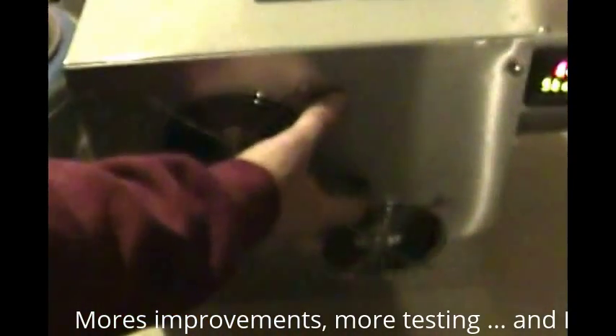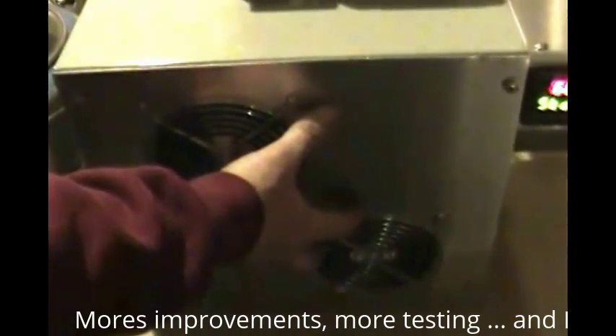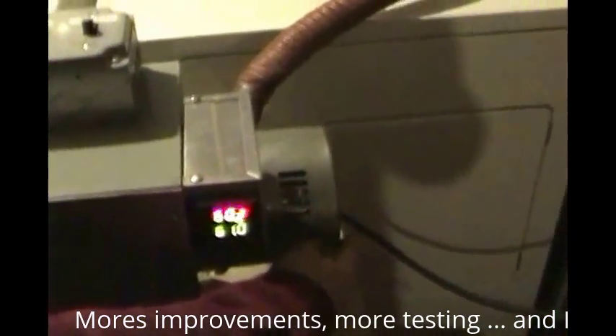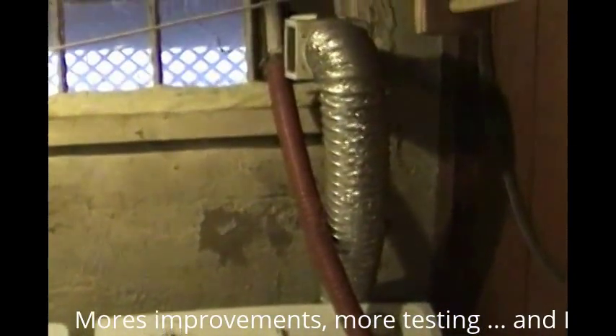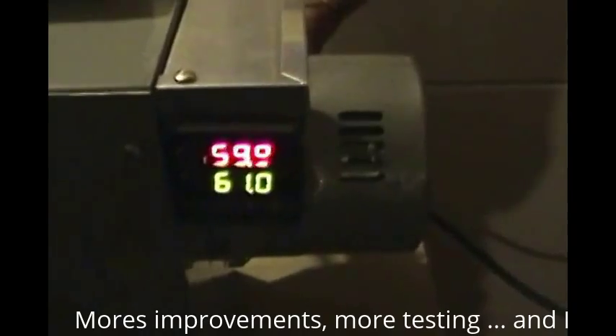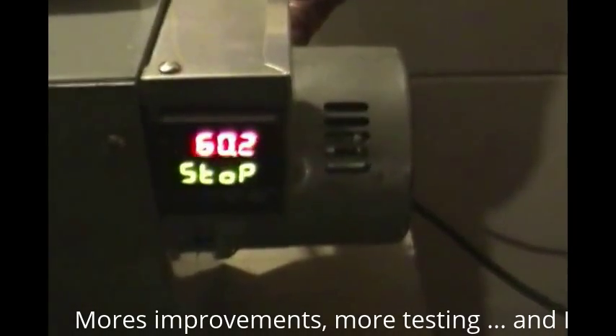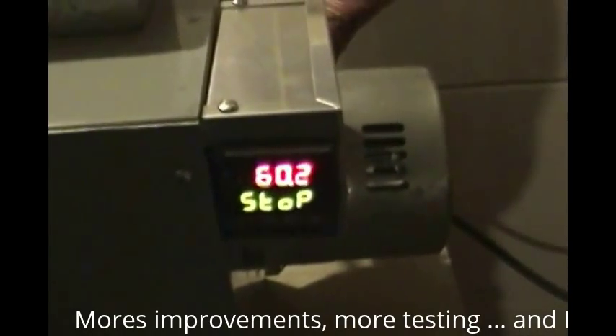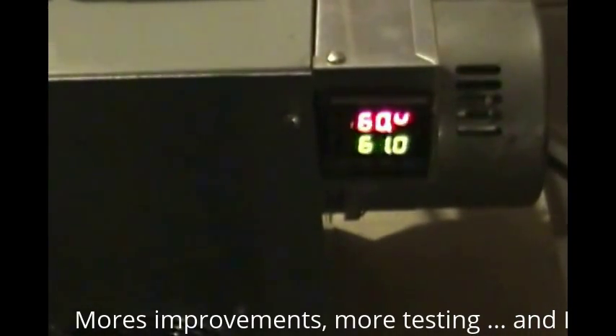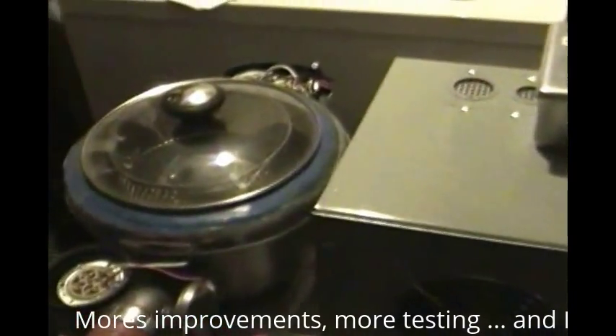There's a special cooling chamber inside of here that cools the exhaust prior to its exiting through the vacuum system that we have, and the hot air and the exhaust just gets shot out through that thin tube outside. Here's our PID. It's programmed to get up to 300 degrees in 5 minutes, so it goes through a type of extended drying phase, and then from there it's going to take 5 minutes to get up to 401 degrees, and at that point it'll automatically turn off the heating elements, and we start the cool down process.